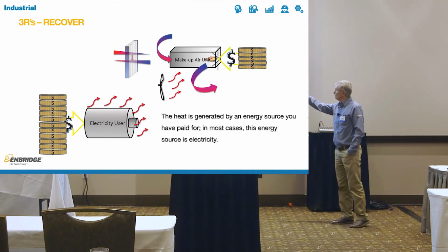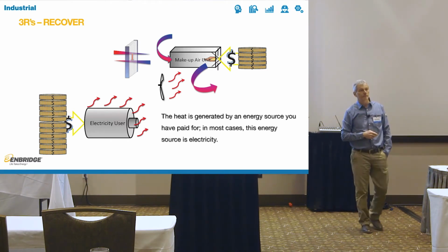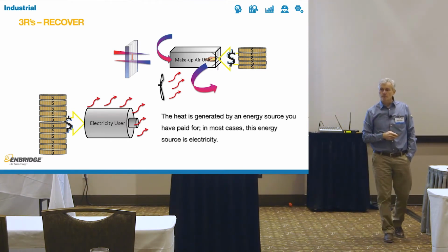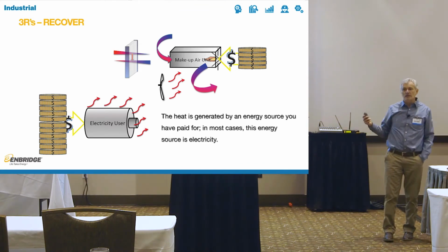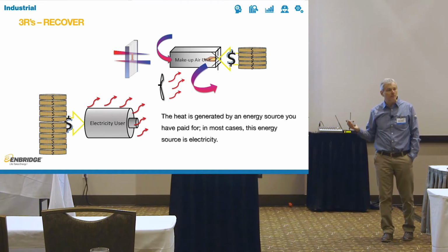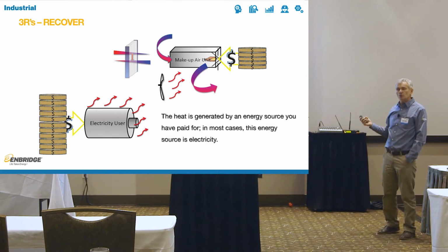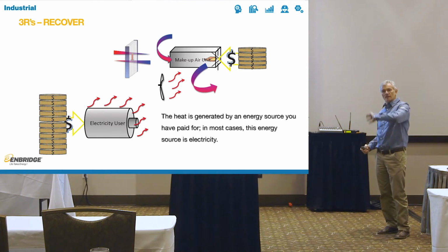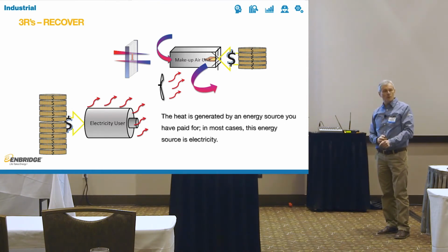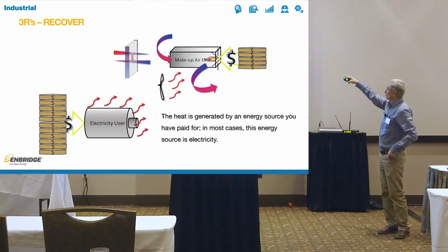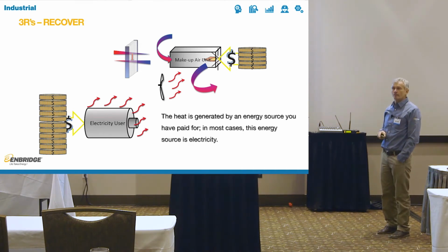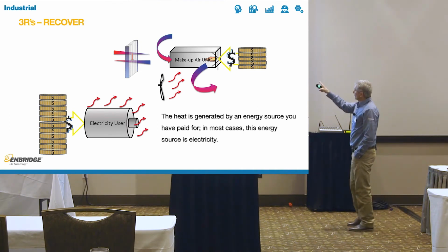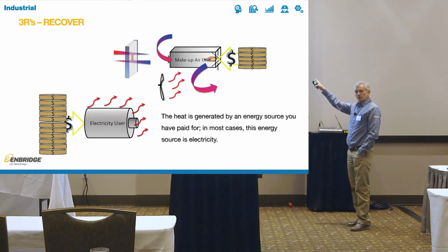What if we just took that heat, put some air socks or a fan, and distributed the heat around the place? And you're talking air compressor heat. It's not like it's polluted or anything. It's just regular heat. Most people have giant big ducts that take that heat and dump it out the door on the other side of the wall, right outside, heating up the area and community. And then they will put a whole bunch of money in the makeup air unit to keep it warm. So why not just do that and reduce the amount of air that the makeup air unit needs to make up the temperature on, and then you'll save the energy.